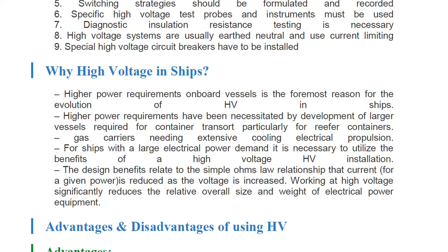High power requirement on board vessels is the foremost reason for the introduction of high voltage on ships. High power requirements have been necessitated by the development of larger vessels required for container transport, particularly for reefer containers — because every reefer container must maintain temperature. Also gas carriers need extensive cooling, and electrical propulsion for ships with large electrical power demand necessitates utilizing the benefits of a high voltage installation.